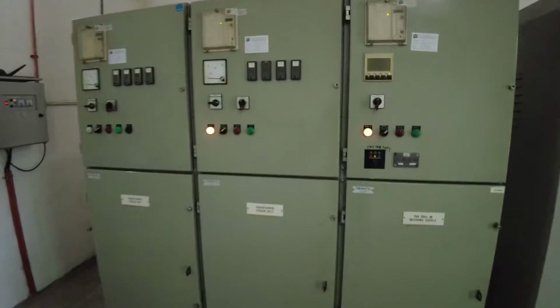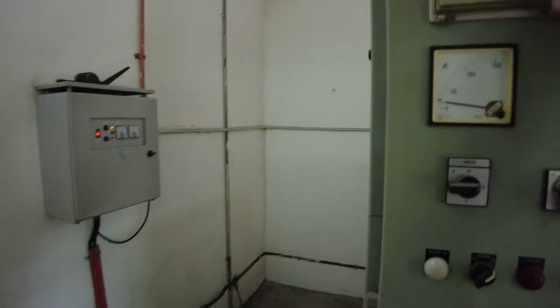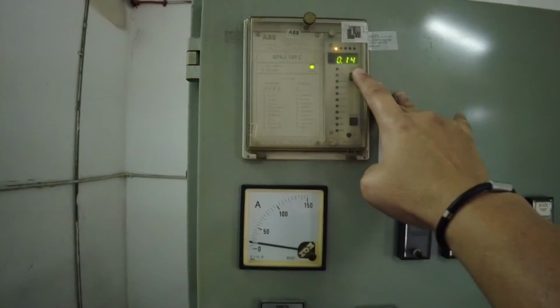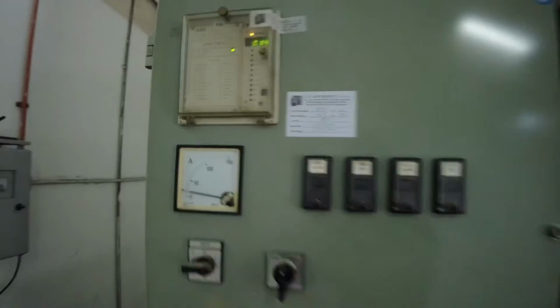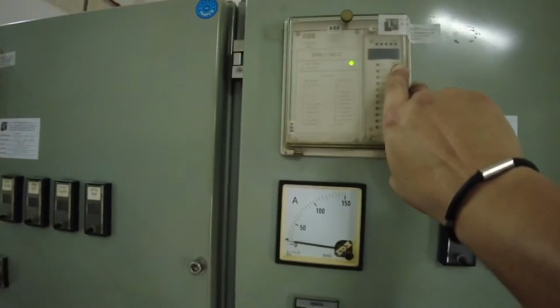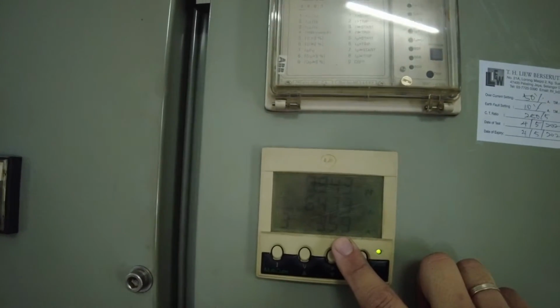Okay, now I'm at the HV room of Ritz Carlton residence. As usual, we're going to check on the installation. This is their HV room. This is transformer number 1 feeder, 14% load. Transformer number 2 feeder, 11% load. Calibration not expired yet. This is the incomer, 15% load, equivalent to 35 amp.